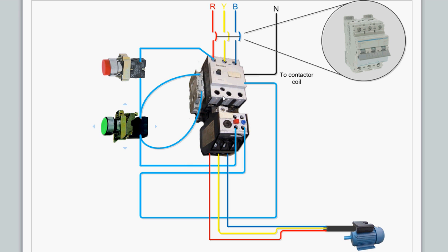Once the contactor activates, the motor starts. This is the hold-on contact—a normally open contact. So once the circuit activates and the current flows from this stop button, it goes here. Now it's a closed contact, so it comes back here and continues through this path, and the motor keeps running.